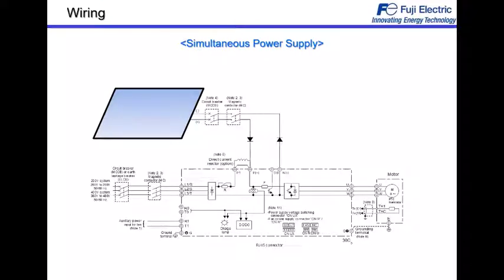And the last is simultaneous power supply. Here we have both connected at the same time. In case of DC, we have the connection through the DC bus of the drive. So before, the positive was at the entrance; now it is the DC bus directly. And we need protection diodes here between the panel and the drive. And of course, AC, we have the AC at the AC input of the drive. But in this case, both are connected at the same time, and it's the drive that selects where to pull the energy from.